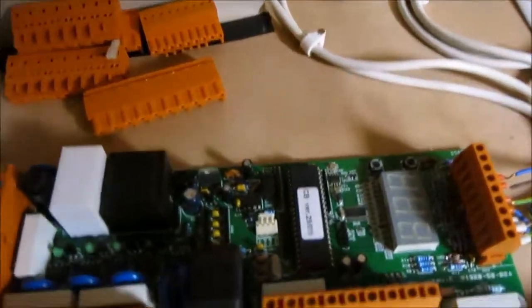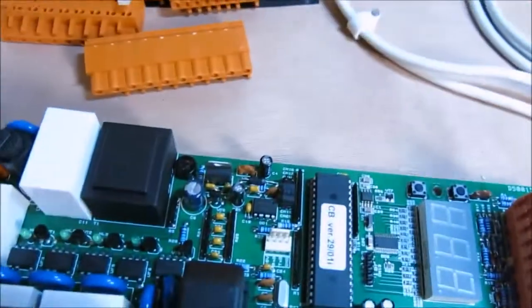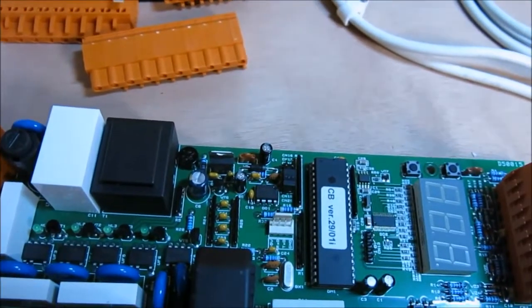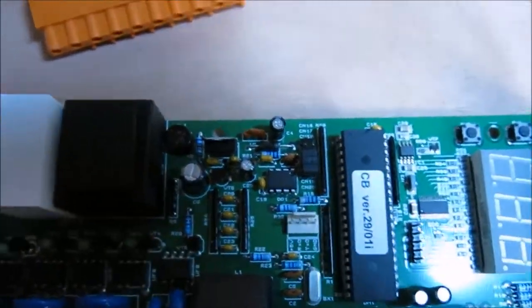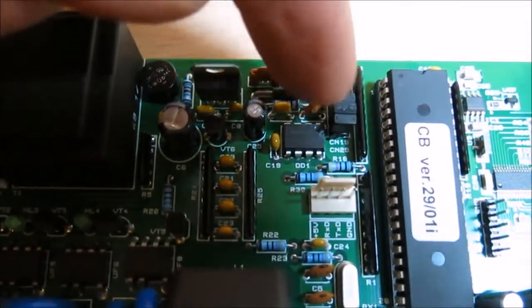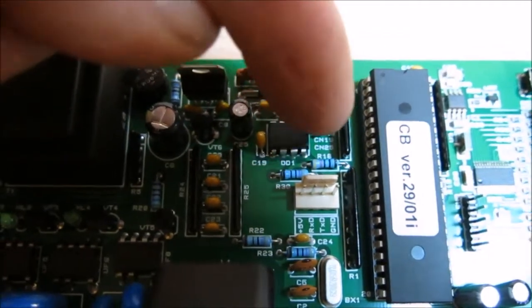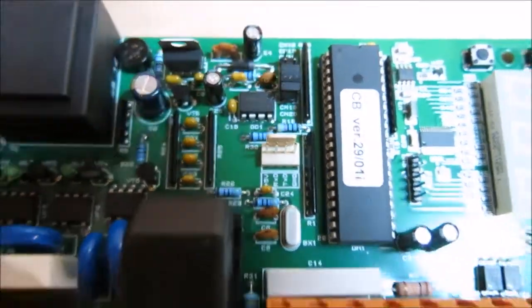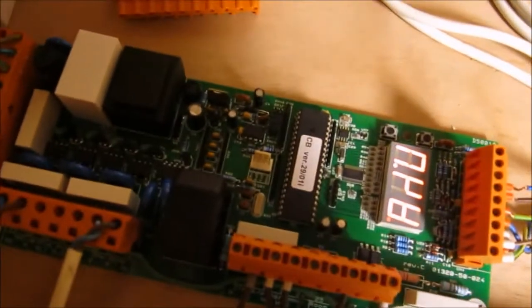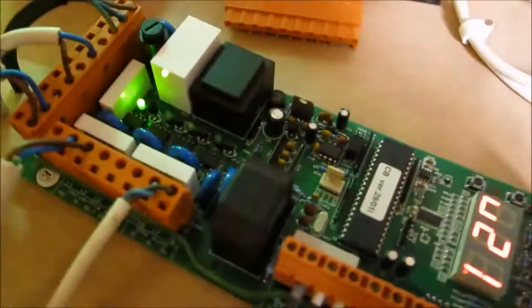Okay, so this is the later version of the software, version 29. It's used as a white label like that, or above. And what you have to do to get the self-test to work on these, on the jumpers, there's 5 sets of jumper headers there. You have to put one of the jumpers on number 5 position, which is this one right over this way. Then when you turn the unit on, you might either get all the segments shown on there or whatever, then it will start going through its self-test.